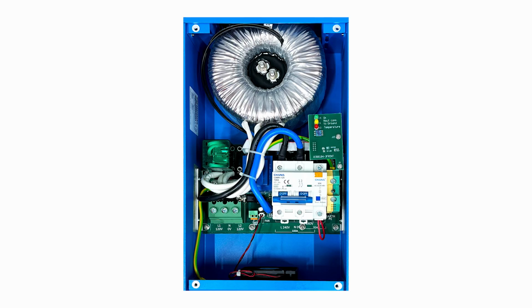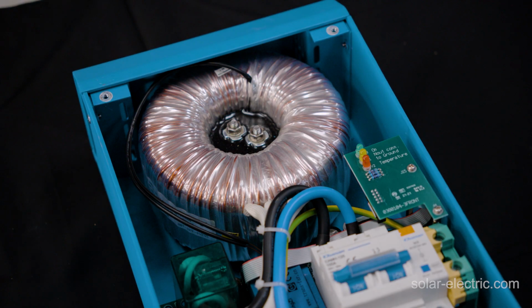Victron Autotransformers have a few limitations regarding current that you should be aware of. First one being the amount of pass-through current. Victron has the 32 amp and the 100 amp autotransformers. For example, with the 100 amp autotransformer, we can have 100 amps pass-through from 120 to 120 or 240 through to 240. The other limitation is the actual transformer inside has a 32 amp limitation. So when we're stepping up, that new leg cannot be pulling more than 32 amps. And vice versa if we're stepping down.